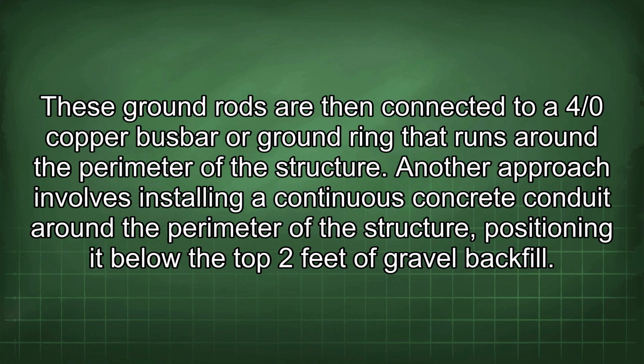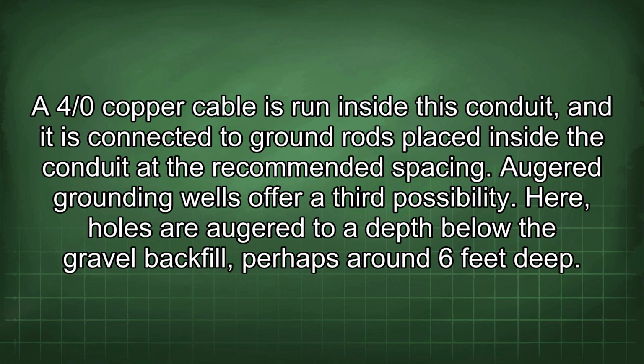Another approach involves installing a continuous concrete conduit around the perimeter of the structure, positioning it below the top 2 feet of gravel backfill. A 4/0 copper cable is run inside this conduit, and it is connected to ground rods placed inside the conduit at the recommended spacing.